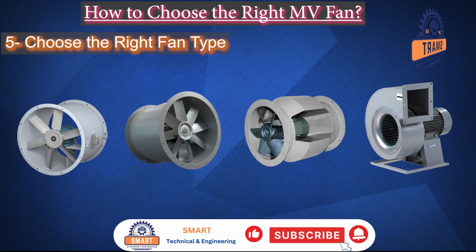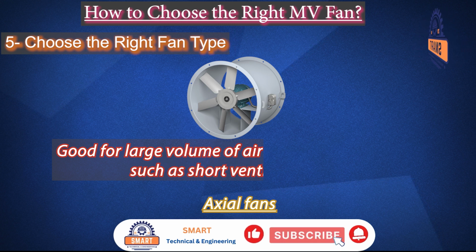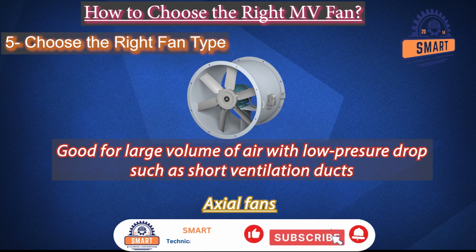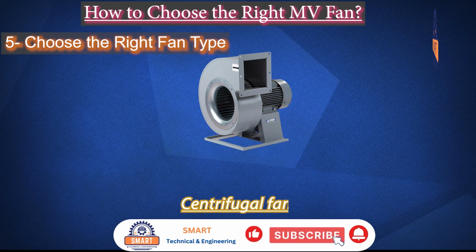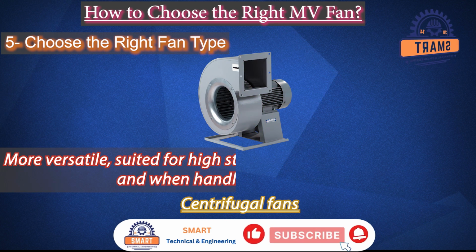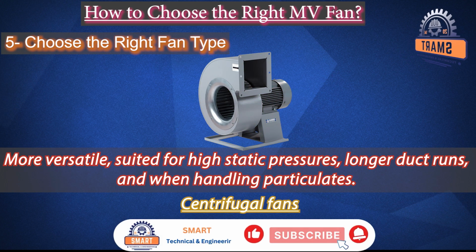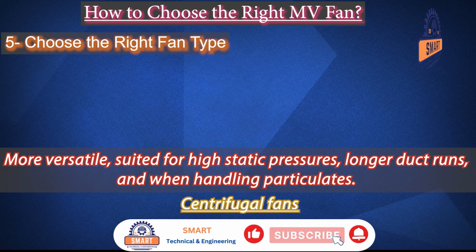5. Choose the right fan type. Now, pick the right fan type. Axial fans, good for large volumes of air with low pressure drop, such as short ventilation ducts. Centrifugal fans, more versatile, suited for high static pressures, longer duct runs, and when handling particulates.